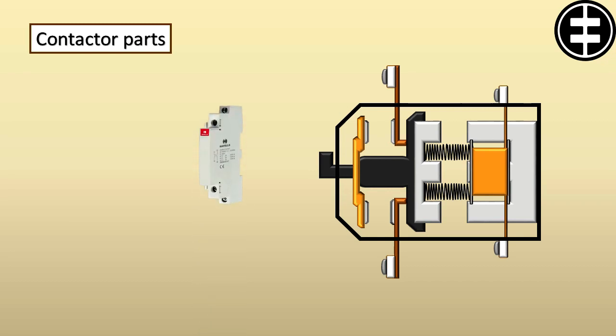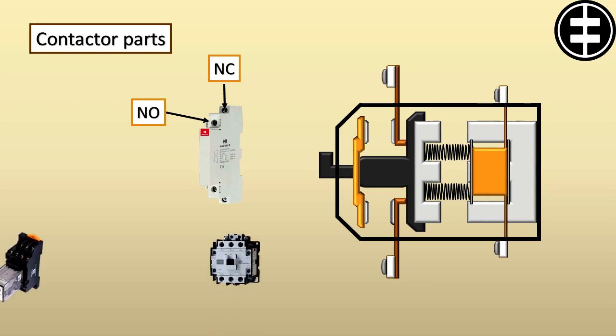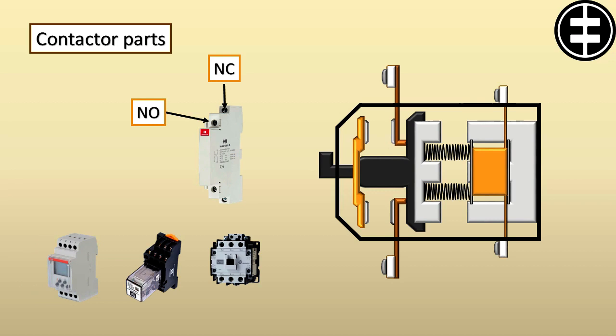Auxiliary contacts could be normally open or closed, and are not designed to carry high load like the main contacts. They allow us to make on and off for light current loads such as contactor coils, relays, timers and many other control circuit parts. They are linked to the contactor mechanism, so when the contactor is energized, they will change status from normally open to closed, and vice versa.